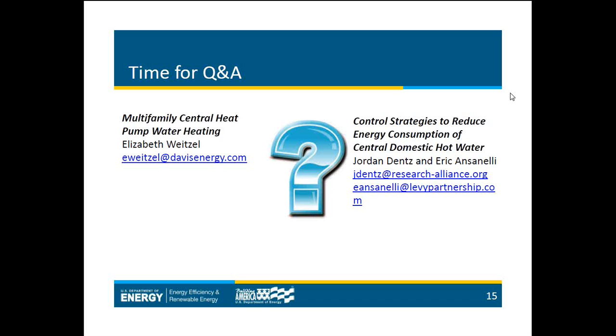And then another question, what kind of flow sensors did you use, and why does per bedroom usage increase so much in winter? We used a few different types of flow sensors. There are the flow switches, which are part of the demand control system, and that's a simple switch. It doesn't measure the flow. That's provided by the manufacturer of the innovative demand control system. To measure flow, we used two different types of systems based on the size of the pipes. We used an ultrasonic flow sensor for the larger buildings, and for the smaller buildings, we used Omega flow sensors.